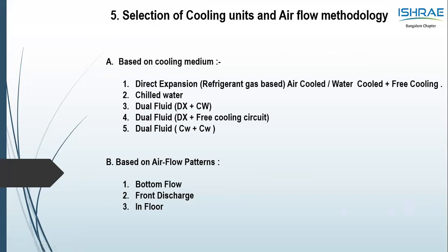Now breaking it further into the different types of cooling methodology based on the cooling medium and the airflow pattern, we will look at that. Direct expansion, air cooled, water cooled, chilled water. The CCUs are also defined into dual fluid, one being direct expansion, refrigerant based, and a chilled water, or DX and a free cooling circuit, or a combination of both of the chilled water. Based on the airflow pattern, bottom throw, frontal throw, in-row, a variety of options are there on the CCU, the unit which goes into the server room.